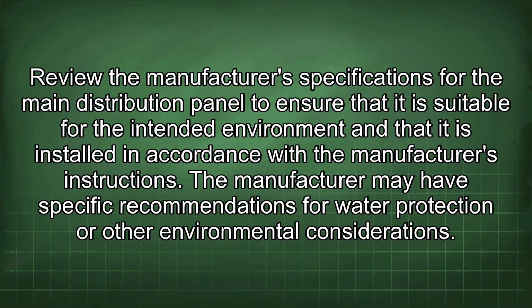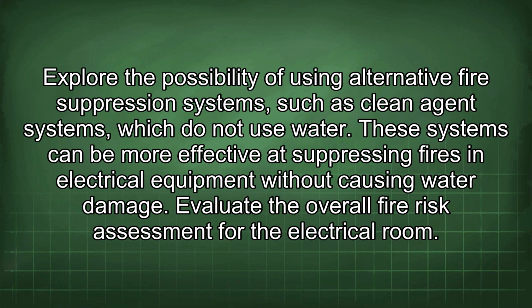Review the manufacturer's specifications for the main distribution panel to ensure that it is suitable for the intended environment and that it is installed in accordance with the manufacturer's instructions. The manufacturer may have specific recommendations for water protection or other environmental considerations. Explore the possibility of using alternative fire suppression systems such as clean agent systems, which do not use water. These systems can be more effective at suppressing fires in electrical equipment without causing water damage.